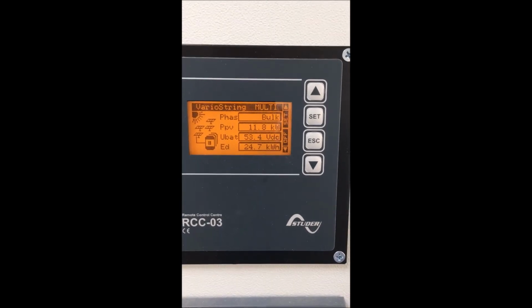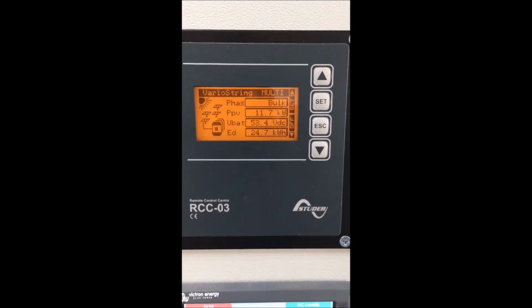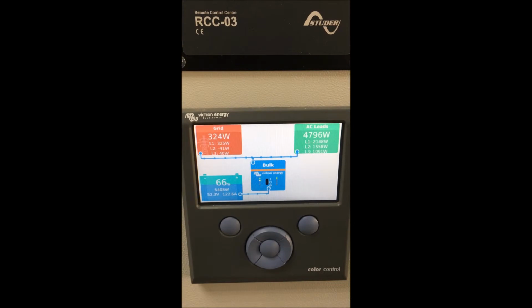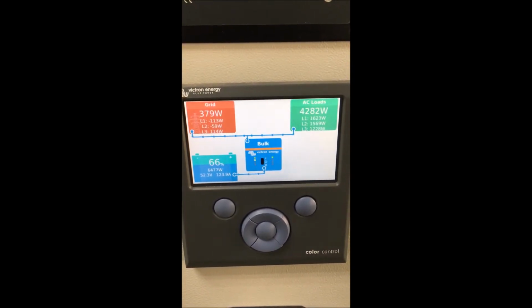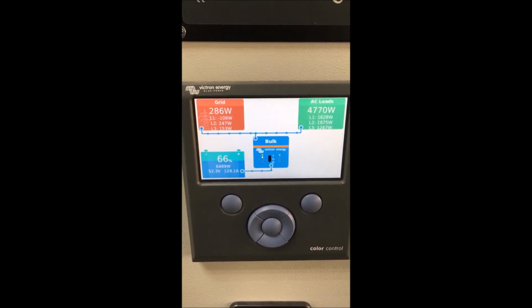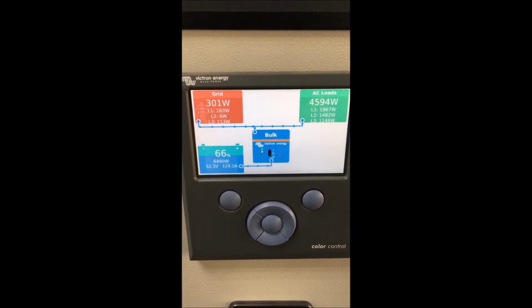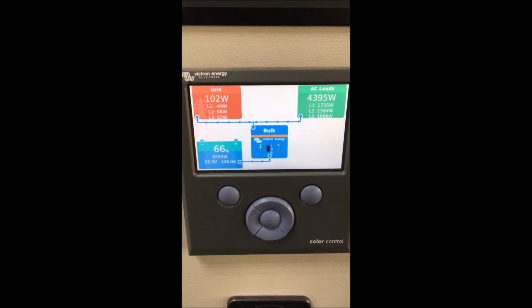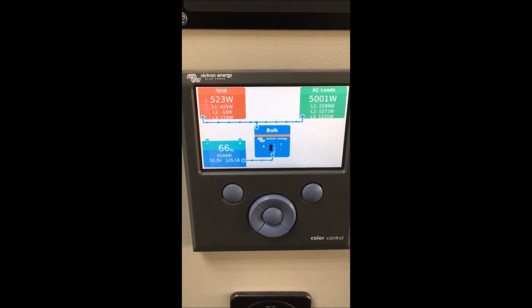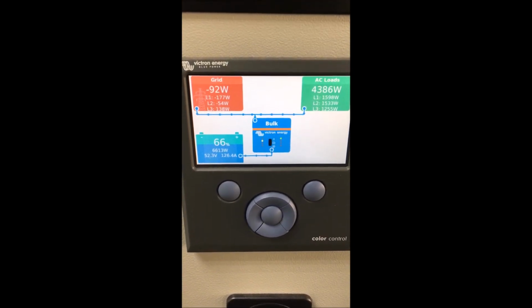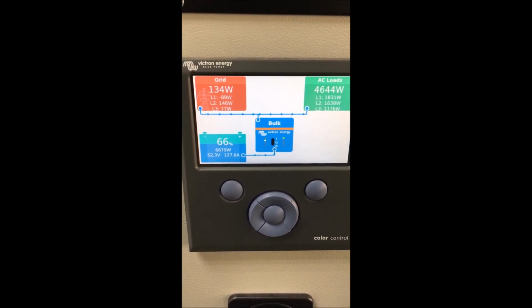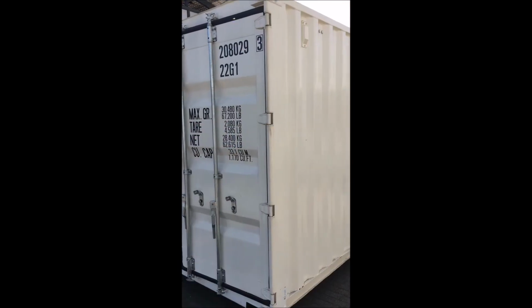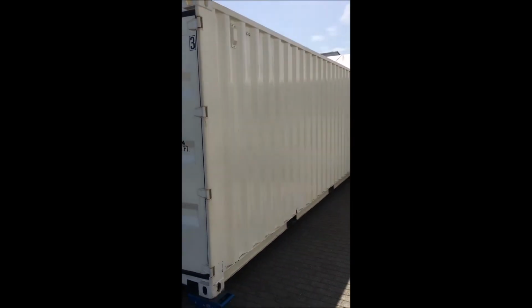So during the daytime, we store extra solar energy in the batteries, and then this energy is dispersed to the load during the nighttime without having to use the grid or a diesel. Of course, when the battery reaches its lower limit, then either a diesel needs to be started or there has to be a grid supply. Now, let's take a look at our containerized systems.